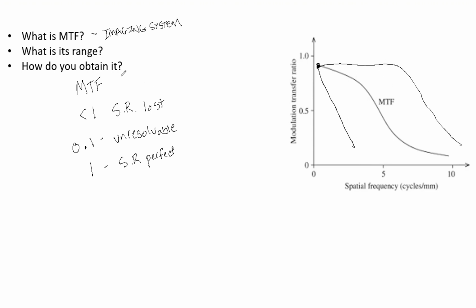So how do you obtain it? You can use the CATphan. There is a QC3 phantom. Mobius has a phantom. Standard Imaging has a phantom. Essentially, it is the Fourier transform of a line spread function. So a sharper line spread function means less spreading and a slower drop off in MTF, which is good. Don't go too much into the weeds, because clinically what we need to know is that there is a phantom, you can scan it, and then there are different software packages that do this Fourier transform of the line spread function and can tell you what the MTF is.